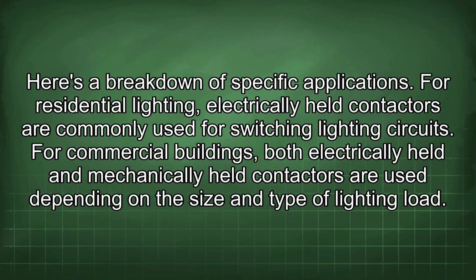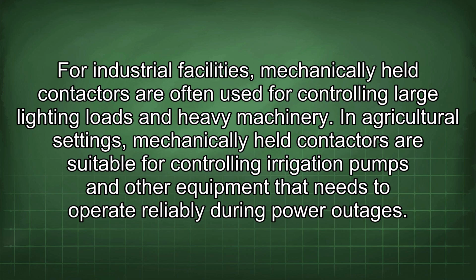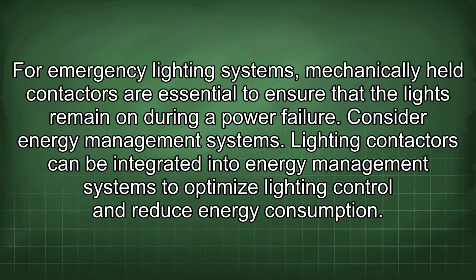Here's a breakdown of specific applications. For residential lighting, electrically held contactors are commonly used for switching lighting circuits. For commercial buildings, both electrically held and mechanically held contactors are used depending on the size and type of lighting load. For industrial facilities, mechanically held contactors are often used for controlling large lighting loads and heavy machinery. In agricultural settings, mechanically held contactors are suitable for controlling irrigation pumps and other equipment that needs to operate reliably during power outages. For emergency lighting systems, mechanically held contactors are essential to ensure that the lights remain on during a power failure.